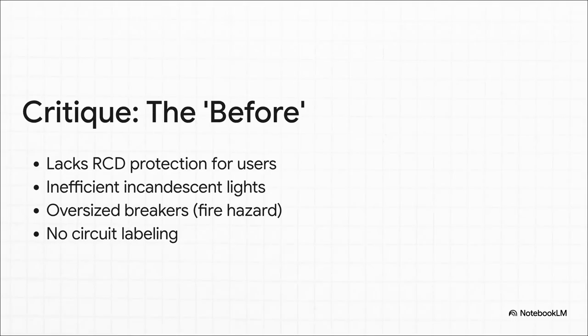Okay, here's our classic before picture. Now that you know what to look for, you can probably spot the problems right away. First, no RCD protection on the outlets? That's a huge shock hazard. Then you've got these old incandescent lights, just massive energy wasters. And look at this, the circuit breakers are too big for the wires they're protecting. That is a massive fire risk, because the wire itself could melt before the breaker even thinks about tripping. And finally, no labels on the panel? That turns finding the right circuit into a dangerous guessing game.